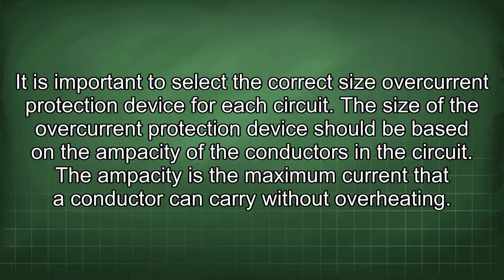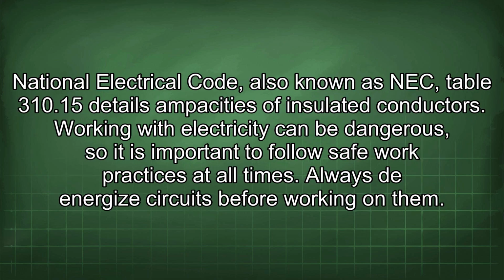It is important to select the correct size overcurrent protection device for each circuit. The size of the overcurrent protection device should be based on the ampacity of the conductors in the circuit. The ampacity is the maximum current that a conductor can carry without overheating. National Electrical Code, also known as NEC Table 310.15, details ampacities of insulated conductors.